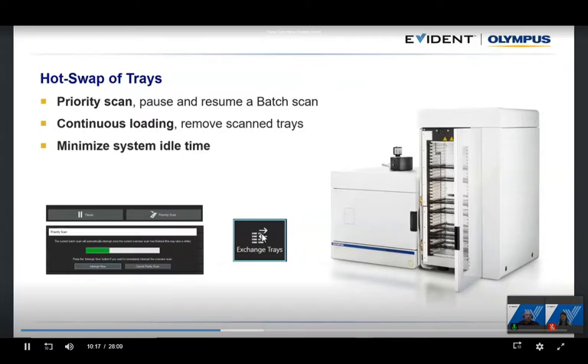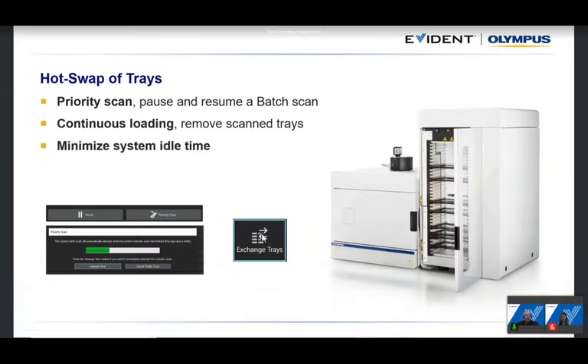In a laboratory you never know what samples are coming. If you have a large batch scan of 200 slides running and someone needs urgent scans, the VS200 has an exchange tray button activating a priority scan function — you can stop the batch, scan the priority slides, then restart the batch without problems. Continuous loading is also supported: trays already scanned can be removed and fresh ones inserted while the system keeps running, minimizing idle time and maximizing efficiency.